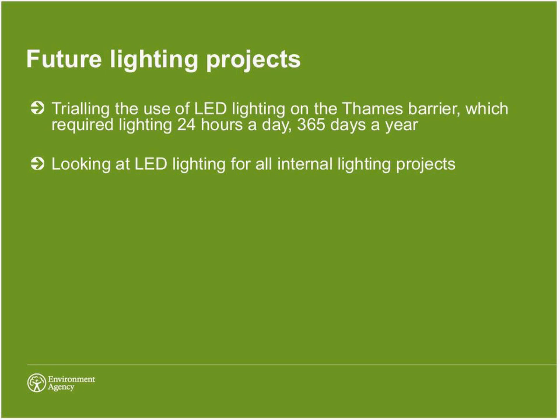Another useful thing that we've seen is we've tended to buy the LED lights that are fitted in parallel, so if one lamp fails it doesn't affect the rest in the group. So lamp failures over time don't have such an impact. And we're looking at replaceable lamp assemblies within the lights internally as well, so if LEDs do fail, we can just replace them rather than the whole fittings. That's a project that's coming up in a month, and I think that's the next phase for us, to really start to introduce it internally.